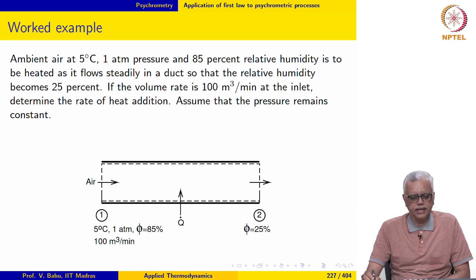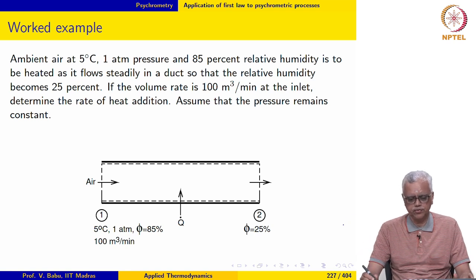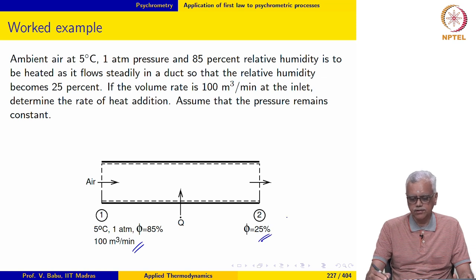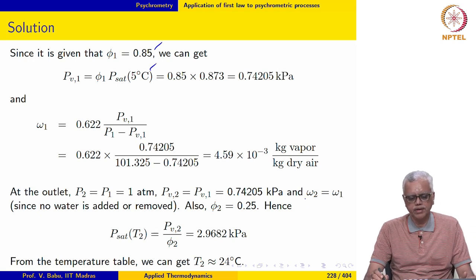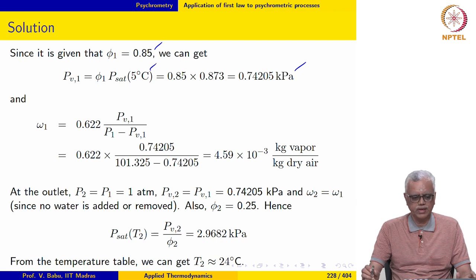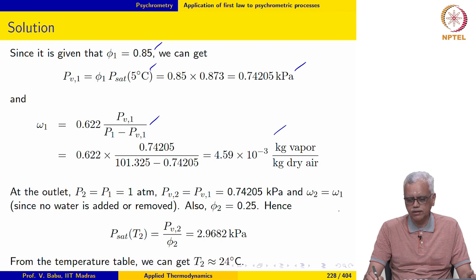First steady-flow example: ambient air at 5°C, 1 atmosphere and 85% relative humidity is heated as it flows steadily in a duct so that the relative humidity becomes 25%. The volume flow rate is 100 m³/min at the inlet; determine the rate of heat addition at constant mixture pressure. At the inlet, Psat(5°C) is looked up and the partial pressure of water vapour is 0.74205 kPa, giving a humidity ratio of 4.59 g of vapour per kg of dry air.